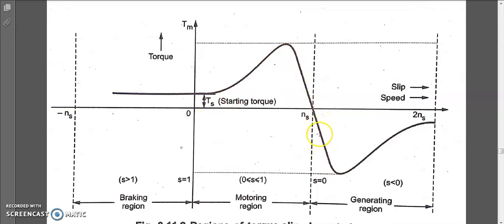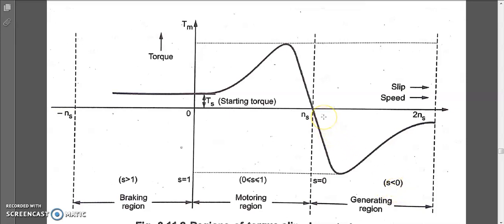In the generating region, the rotor runs at greater than synchronous speed, so slip is less than zero — negative. Since s equals ns minus n and n is greater than ns, the result is negative. To operate the motor as an induction generator, run the rotor above synchronous speed. In the generating region, the motor takes mechanical input and delivers electrical output to the stator.